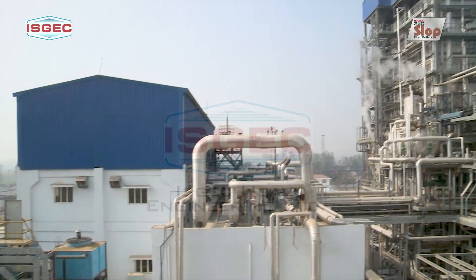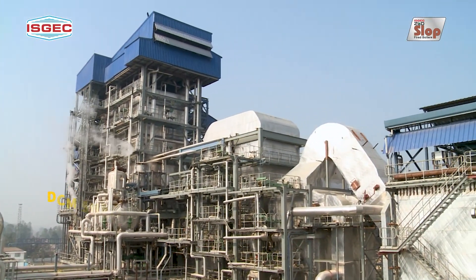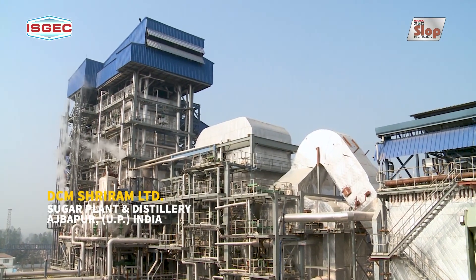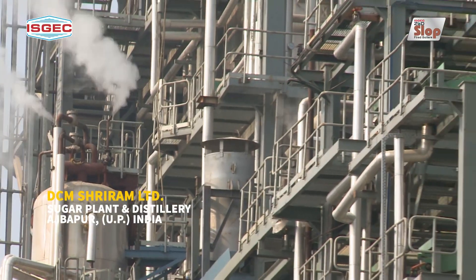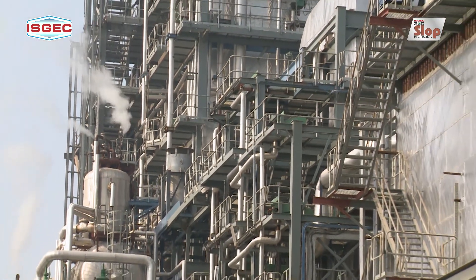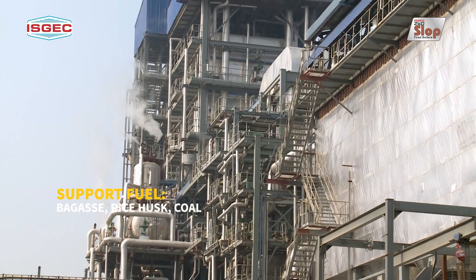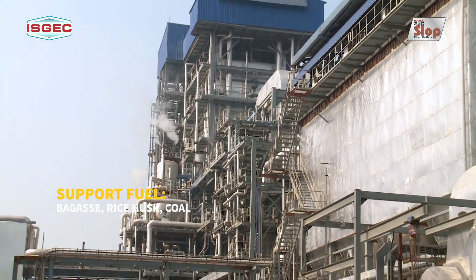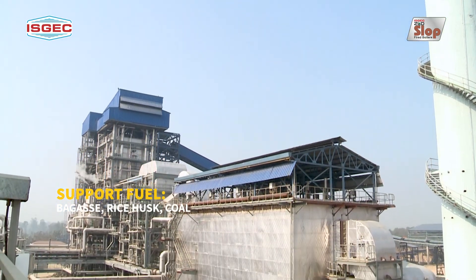Welcome to one of the world's largest slop-fired boiler installations at the DCM Sriram Limited sugar plant and distillery at Ajbapur in Uttar Pradesh, India. The boiler has been designed for a capacity of 80 tons per hour and is being operated at 33.9 tons per hour slop at 60 Brix, with bagasse, rice husk and coal as support fuel.